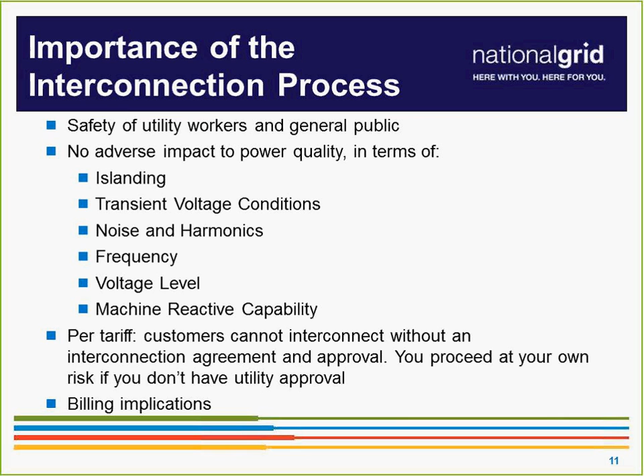We start with the pre-application report. You have to provide all of the information for us to do this: the DG size, whether it's standalone, the service, minimum and maximum site load, whether the service needs to be upgraded, how it impacts the meter, what circuit and voltage the customer's load will be serviced off of, whether it's three-phase, what load is active right now on the feeders, what's being requested so you know how much capacity is already committed and how much is being requested, and other constraints on that feeder where you're potentially interconnecting.